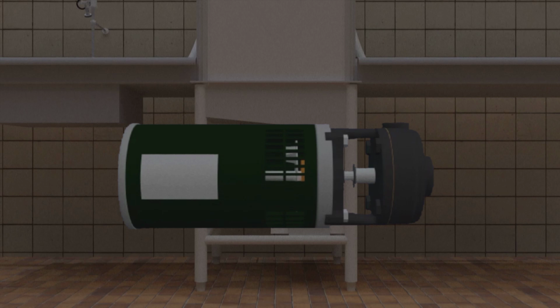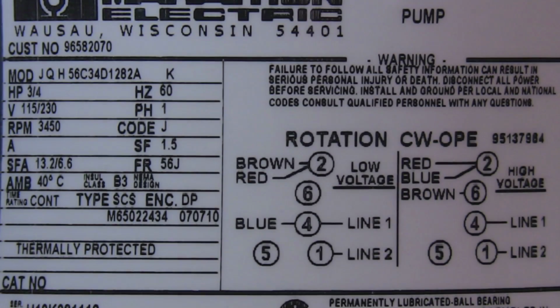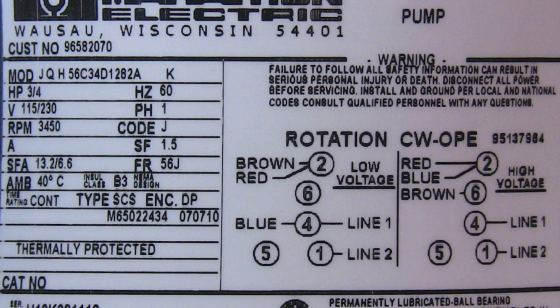Once the cover is removed, several electrical terminals are revealed. Look closely and you will see the terminals are numbered 1 through 6. These numbers are landmarks for ensuring wires are connected to the correct terminals, but more about this shortly. The last item to examine is the motor's data plate, which is a sticker that provides key information about proper installation and operation. Sometimes the motor will appear to be missing its data plate. In these instances, it's often covered by a protective film the same color as the motor's body and needs to be removed.